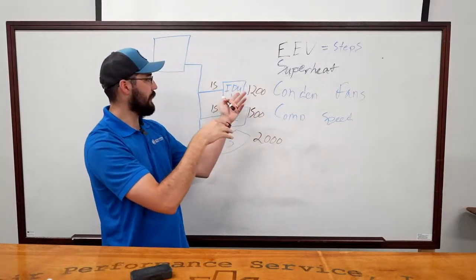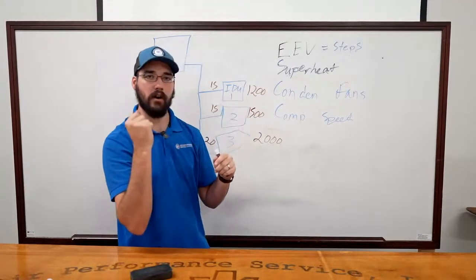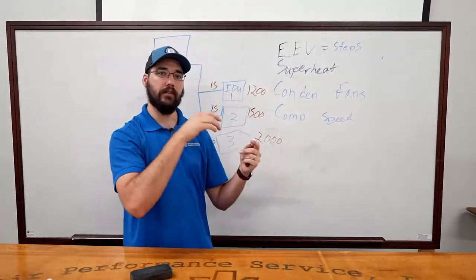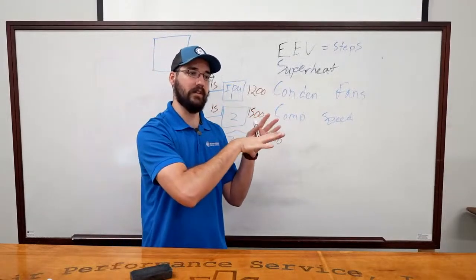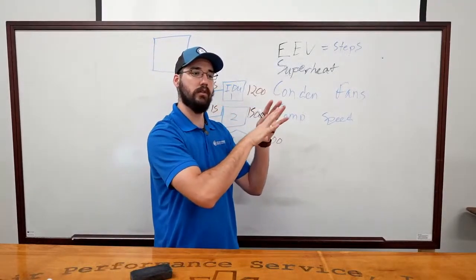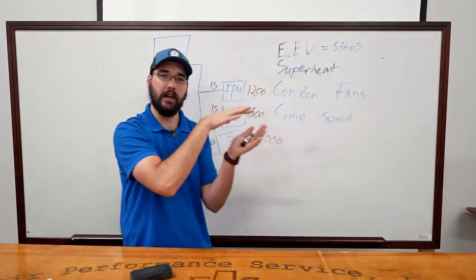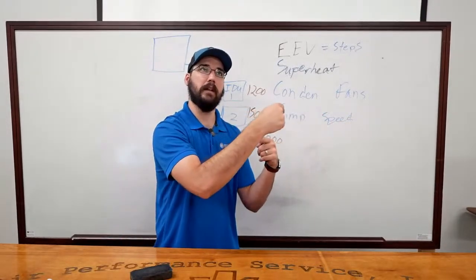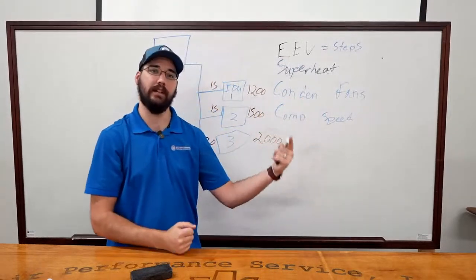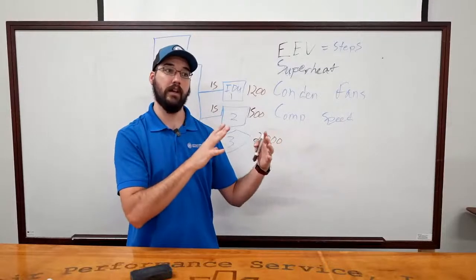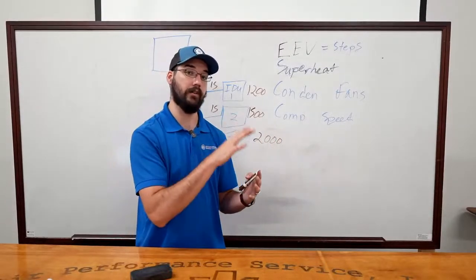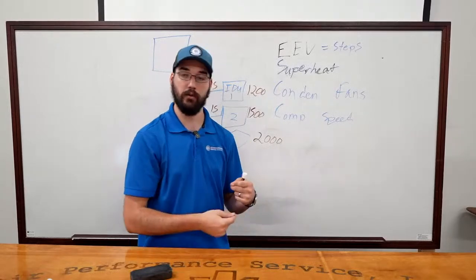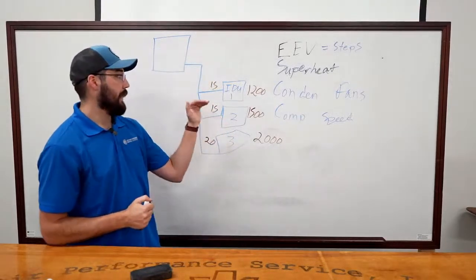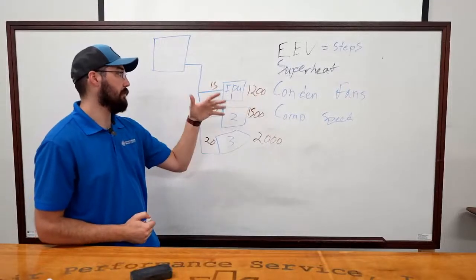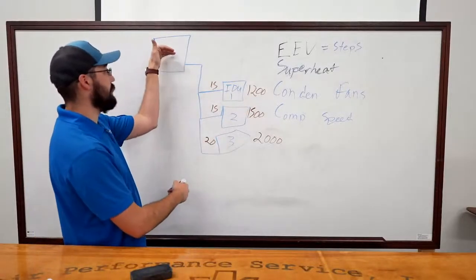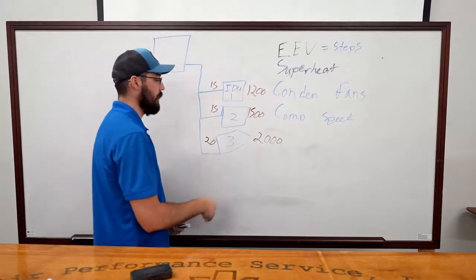And so these valves and the leaving air temp, it's not just an off-on type of operation. Part of its goal is, once it gets to set point, it wants to run for an extended period of time and just kind of hover there, so that it's cooling as much as the space needs it to cool. That's why it's best to leave the fans in auto so they can vary on their own to match whatever the return load conditions are. And it's going to modulate its superheat, the valve position, and everything that it needs to. And the condenser is just responding to whatever is happening down here.